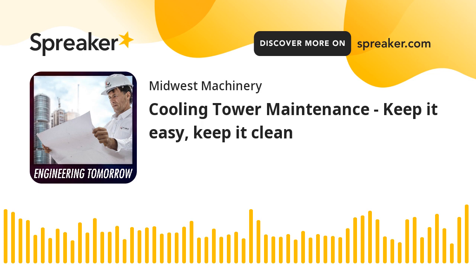Okay, so we've galvanized the tower, now what? Now you really need to look at a chemical treatment company. They're going to need to come up with a water treatment program. As mentioned earlier, you've seen in the news about Legionella getting into your towers. Well, that's going to be in the water. What happens with towers is it's an open source, so a lot of dirt and debris can get in, providing a food source for bacteria that will grow. The bacteria will then start in your cooling tower, and it might make its way down into your HVAC system. But by eliminating your bacteria in the tower, you would hopefully rid your system of that Legionella bacteria.